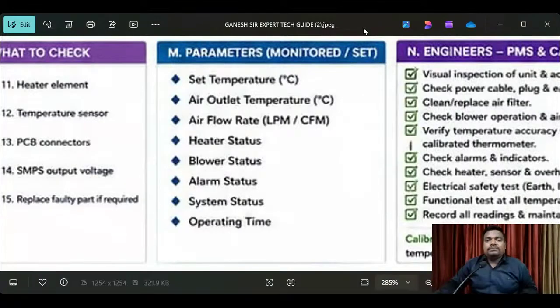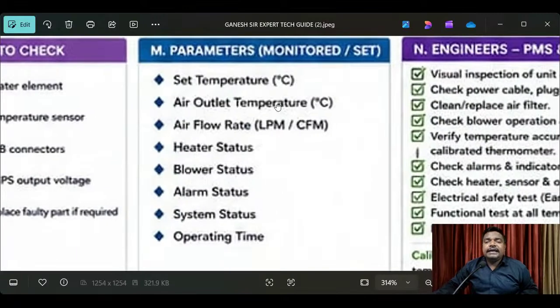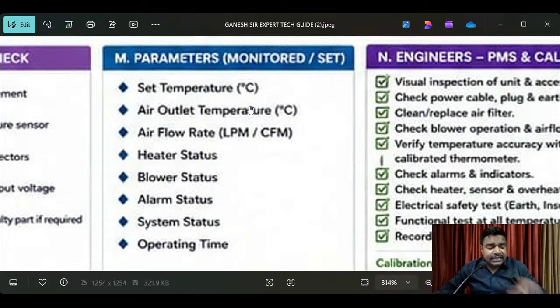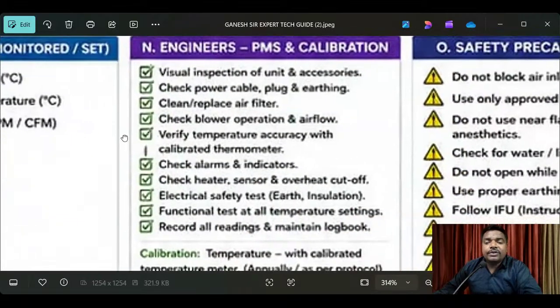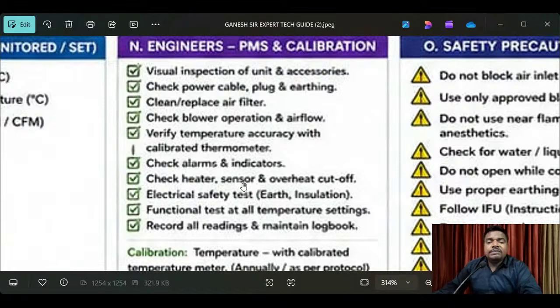Parameters to monitor, see here. I have explained all these things in this slide, but these points apply when you come to the internal parts, when you open the equipment, that is the patient warmer, sorry, the patient warmer monitoring equipment. See, set temperature, air outlet temperature, airflow in LPM or CFM, heater status, blower status, alarm status, system status and operating time. These are the very important points I am sharing here, and it is very important to keep them in mind. I have also given information for PM and calibration purposes.